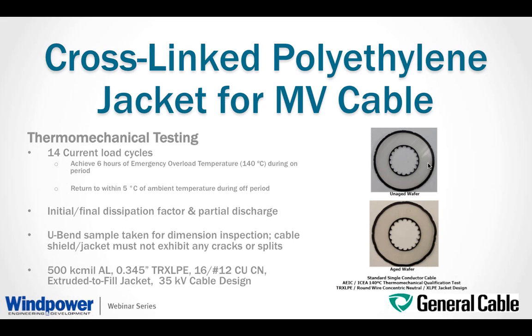You would typically qualify the test samples. The size of the test sample would typically be a 500 kcmil, 35 kV aluminum construction, and with this size you would qualify the complete range of product sizes. Then you have to qualify each type of construction, like a combination of TRXLPE insulation with concentric neutral with an extruded to-fill jacket. So here we ran some comparative testing on this size with an extruded to-fill thermoplastic PE jacket compared to an extruded to-fill thermoset XLPE jacket.